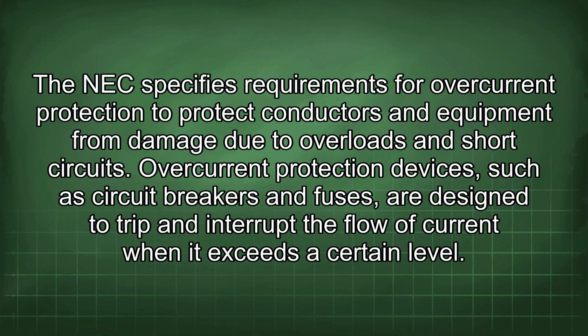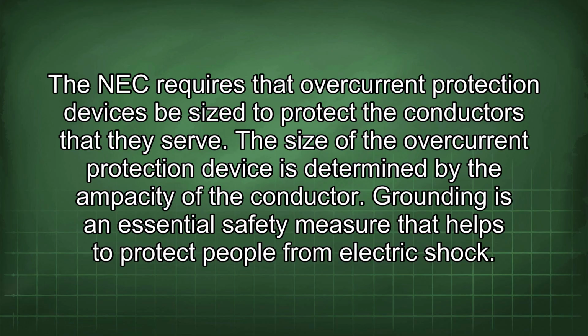The NEC specifies requirements for overcurrent protection to protect conductors and equipment from damage due to overloads and short circuits. Overcurrent protection devices, such as circuit breakers and fuses, are designed to trip and interrupt the flow of current when it exceeds a certain level. The NEC requires that overcurrent protection devices be sized to protect the conductors that they serve. The size of the overcurrent protection device is determined by the ampacity of the conductor.